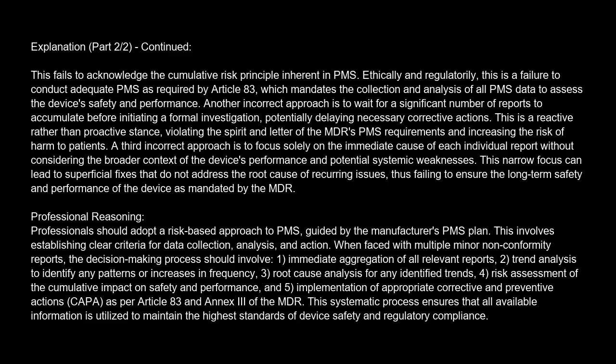A third incorrect approach is to focus solely on the immediate cause of each individual report, without considering the broader context of the device's performance and potential systemic weaknesses. This narrow focus can lead to superficial fixes that do not address the root cause of recurring issues, thus failing to ensure the long-term safety and performance of the device as mandated by the MDR.